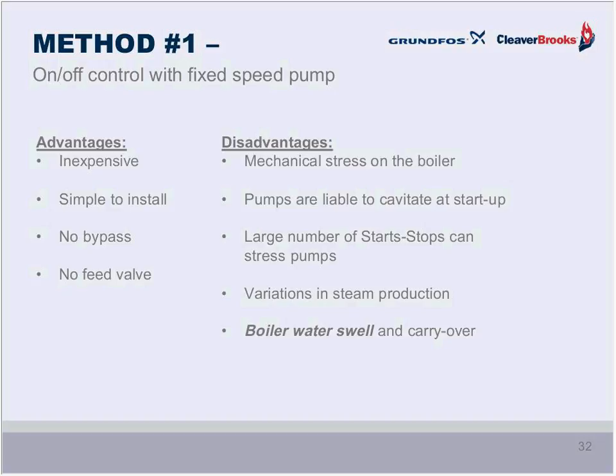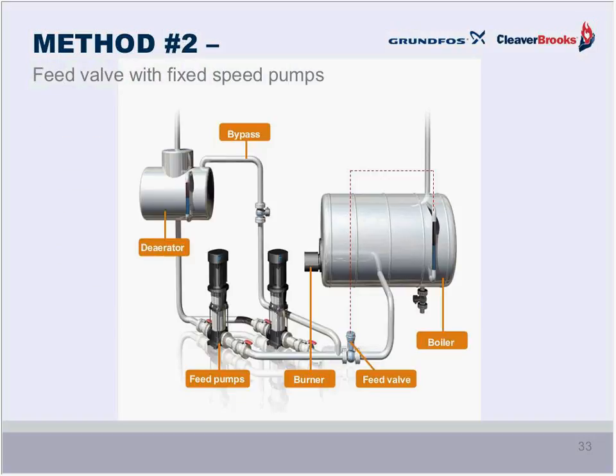Okay, now let's take a look at the second method. There's a feed valve that we've introduced here, if you look in the lower right-hand corner, and that feed valve opening and closing is also controlled by a level sensor on the boiler. That feed valve controls the water intake from these fixed-speed pumps. And, of course, the intake is adjusted according to the steam production.